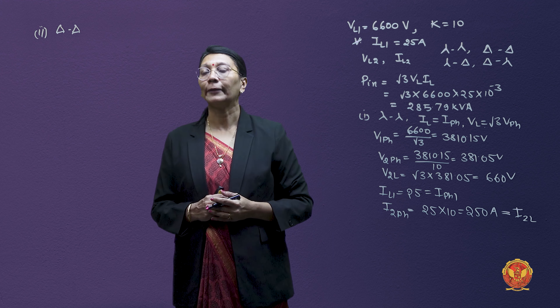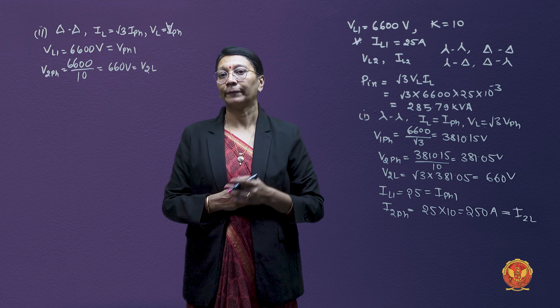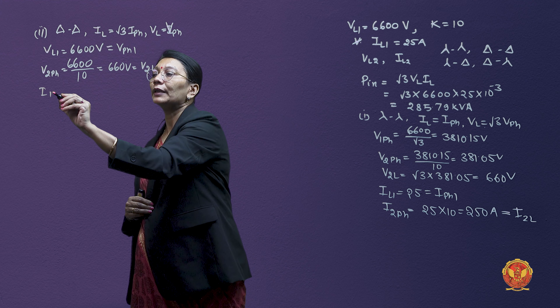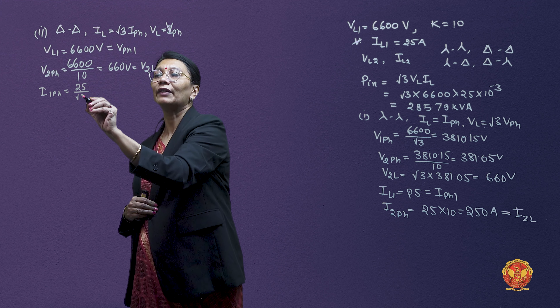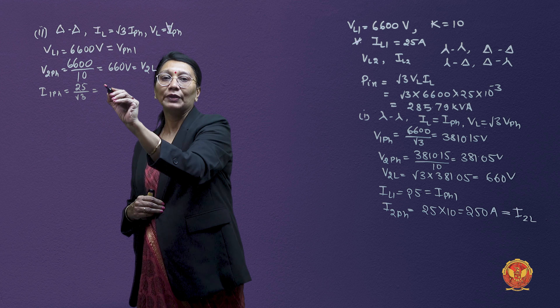For the delta-delta current calculation: in delta, phase current = line current ÷ √3. The primary line current is 25 A, so the primary phase current = 25 ÷ √3. The secondary phase current I2 phase = (25 ÷ √3) × 10. The secondary line current I2 line = √3 × I2 phase = (25 ÷ √3) × 10 × √3 = 250 amperes.